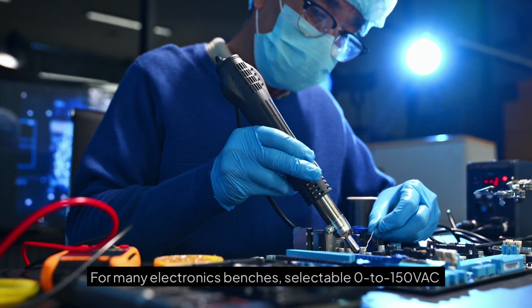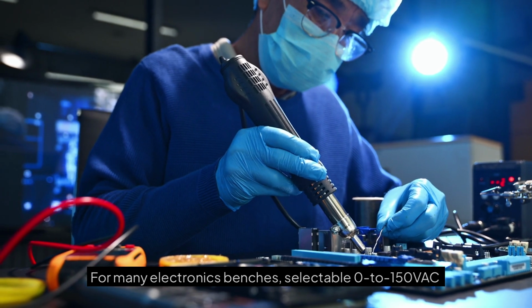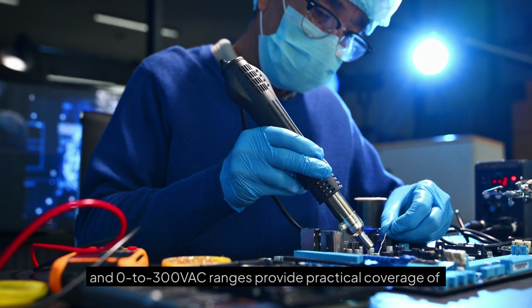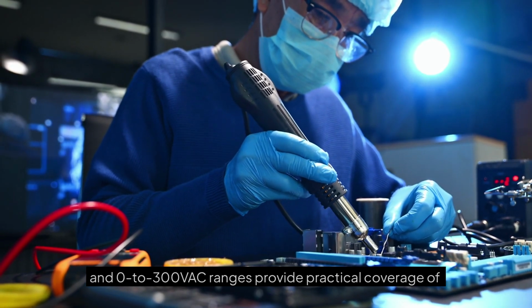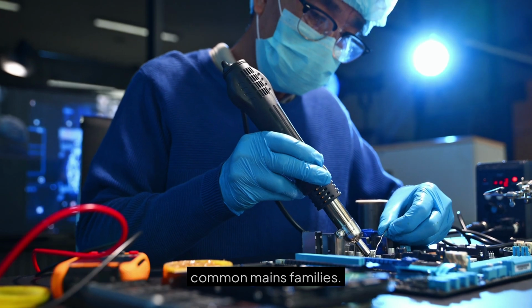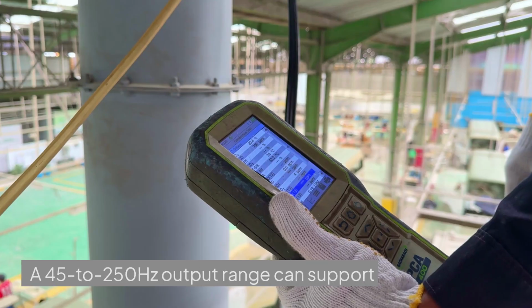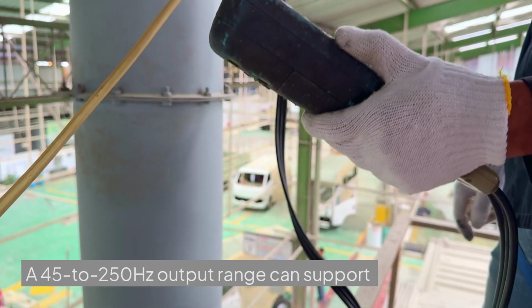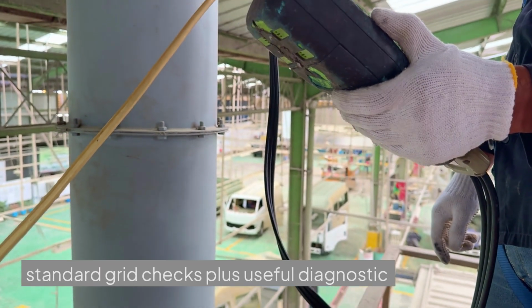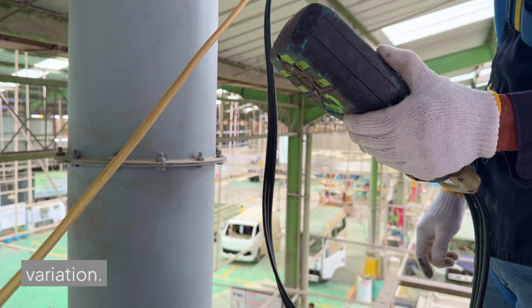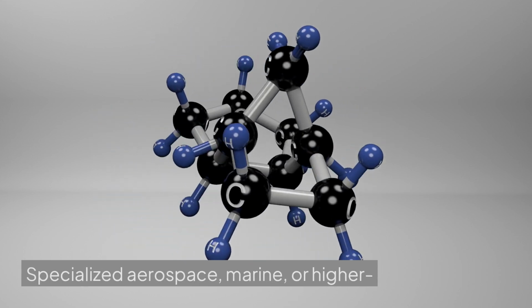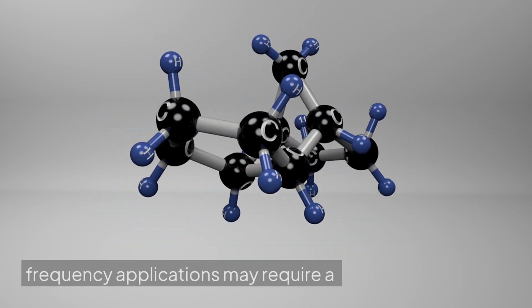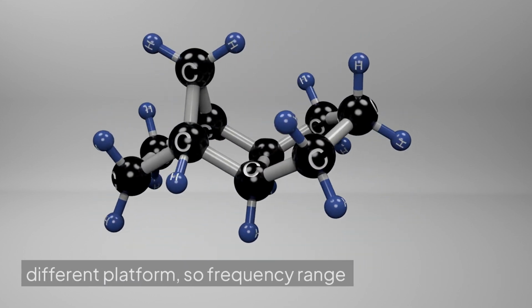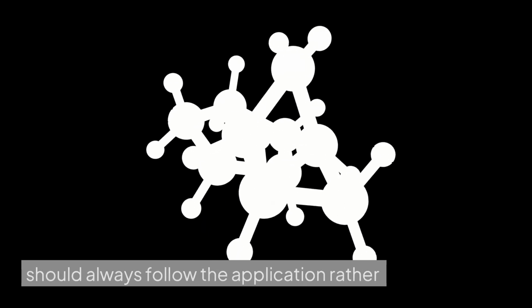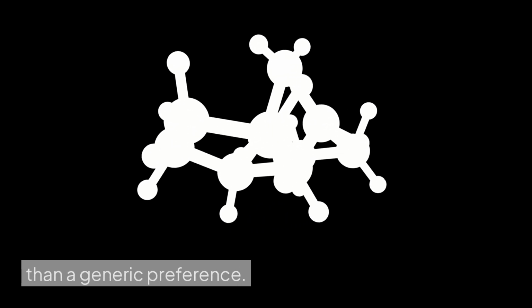For many electronics benches, selectable 0 to 150 VAC and 0 to 300 VAC ranges provide practical coverage of common mains families. A 45 to 250 Hz output range can support standard grid checks plus useful diagnostic variation. Specialized aerospace, marine, or higher frequency applications may require a different platform, so frequency range should always follow the application rather than a generic preference.